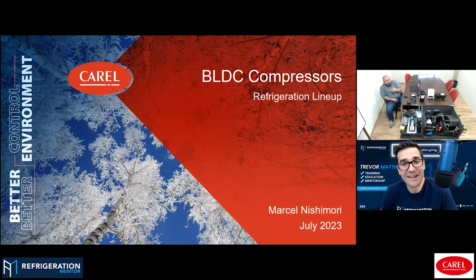Yeah, this is how we operate. We try to understand first what type of application the customer is doing, which kind of compressors or which kind of system they are trying to fix. What is the problem? In general we receive very generic calls. Oh, my unit is not working. Okay, your unit is not working, but specifically is it the evaporator that's not working, the compressor, the valve? Then we start to collect information from the field. What is the superheat reading? What is the pressure you are reading? What is the evaporation temperature? What is the evaporation pressure? And you start to correlate information and make your analysis in order to understand what could be the problem.